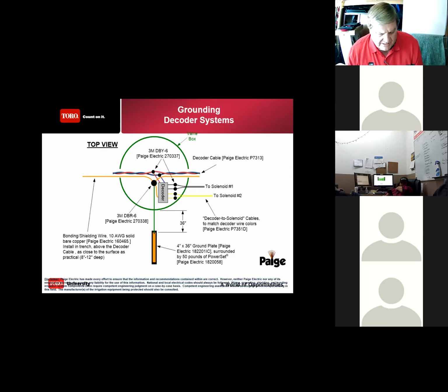So now there is a device. Paige Electric makes it. It is clever. I've seen it used many times, and when I go out to troubleshoot, it makes my job really easy. It's a little device you install on the 2-wire path that connects to the decoder at an intersection with the 2-wire path so that it can isolate different directions of the 2-wire path. So when you're troubleshooting, I can shut that leg off and troubleshoot the rest. And I'll show you some pictures of such a device later on here, depending upon our time.